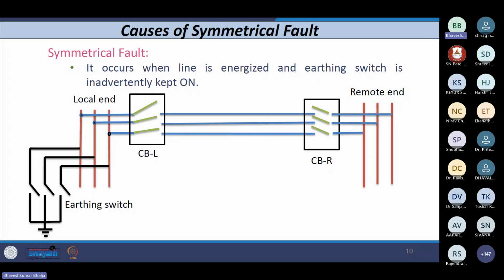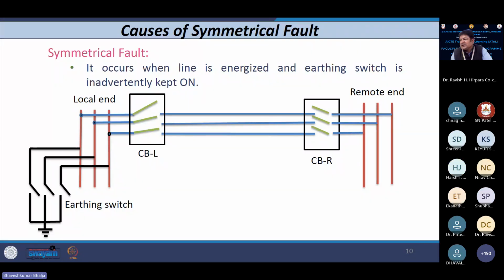Now, if you consider the symmetrical fault, nowadays symmetrical faults are very rare. Earlier they occurred 10, 12, 13, 15 years ago. Nowadays they do not. The reason why a symmetrical or three-phase fault occurs is that we use an earthing switch at each end, either sending end or receiving end, or local end or remote end. Whenever something goes wrong and a fault occurs, we need to open the circuit breaker at the local end, and the same way the circuit breaker at the remote end.